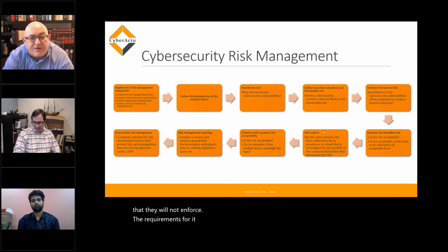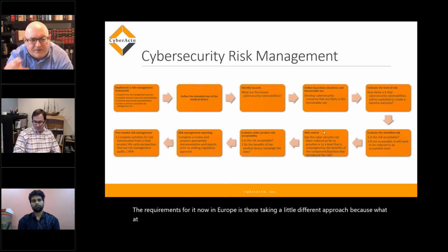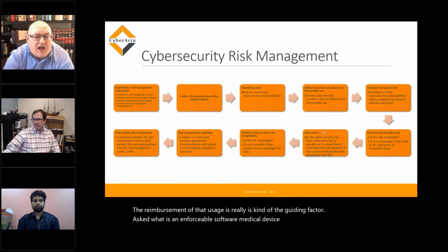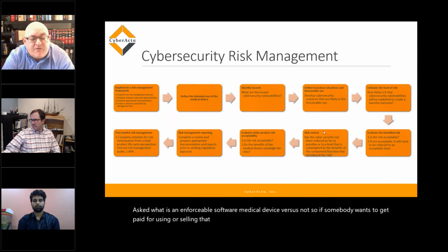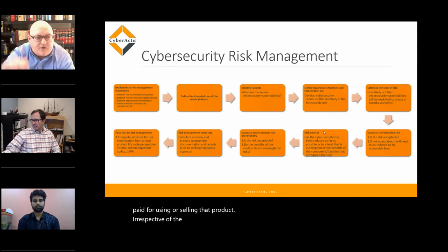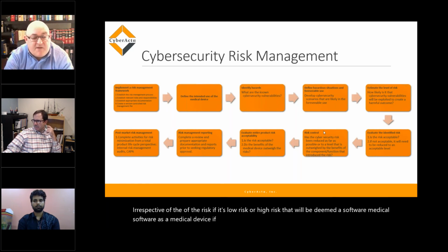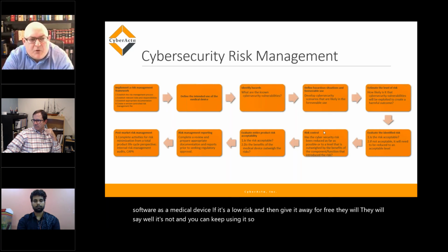Now, in Europe, they're taking a little different approach, because at least in some countries they take a different approach. So in Spain and Germany, the reimbursement of that usage is kind of the guiding factor as to what is an enforceable software medical device versus not. So if somebody wants to get paid for using or selling that product, irrespective of the risk, if it's low risk or high risk, that will be deemed a software as a medical device. If it's low risk and they give it away for free, they will say, well, it's not, and you can keep using it.